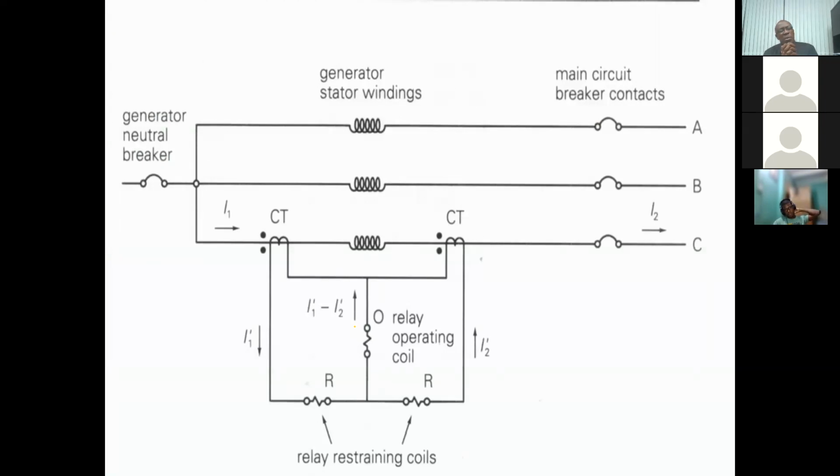What we will look at is your high impedance differential. In other words, we said before that the fault current, regardless of where the fault is, is going to have to be supplied by your generators and motors on the system, etc. So you will have what we refer to as through faults, and this may be best, well, let me use a generator. You have a through fault.